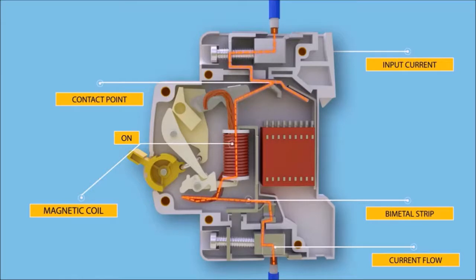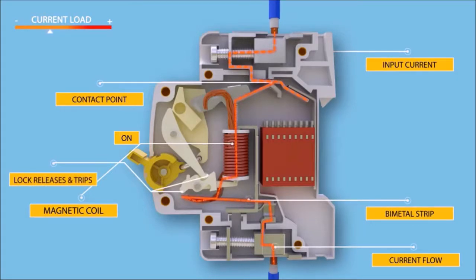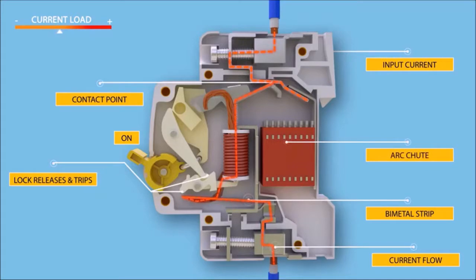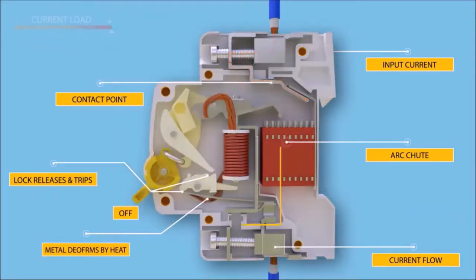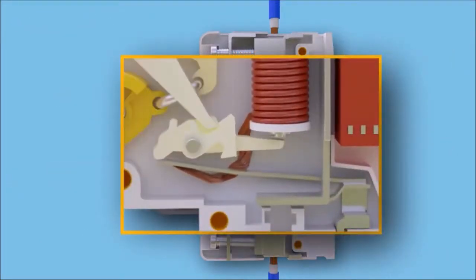Under overload condition, the current through the bimetallic strip causes its temperature to rise. The heat generated within the bimetallic strip is enough to cause deflection due to thermal expansion of metals. This deflection further releases the trip latch and contacts get separated. The visual indication of this trip can be observed by automatic movement of the operator to off position. In tripping operations, an arc is formed when the contacts start separating. This arc is then forced into the arc chute plates, where the arc is split into a series of arcs and at the same time energy is extracted and it cools. Closer look at how the tripping mechanism works.